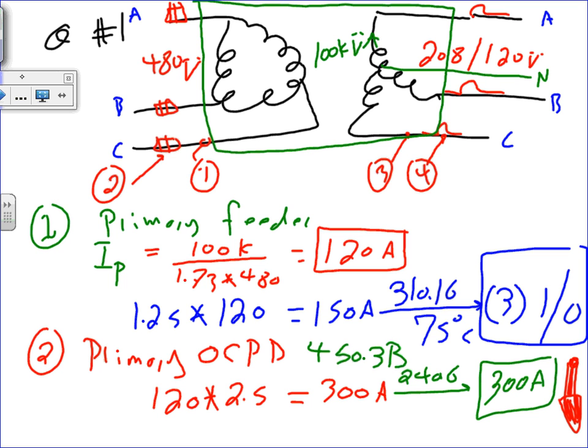Now on this side, I can go land a 150 amp panel here. A 150 amp panel on the secondary side. I'm not going to talk about the panels, guys, because when we land a panel on the secondary of a transformer, there are a few tweaks that I like to do. But you can think of it that this 1/0 can land on a 150 amp panel, feeding it. Okay, before I leave this, I will bring your attention, my friends, to grounding here. If I want to use bonding and grounding, this block here is my ground. This is my neutral. I'm bonding the ground to the neutral.